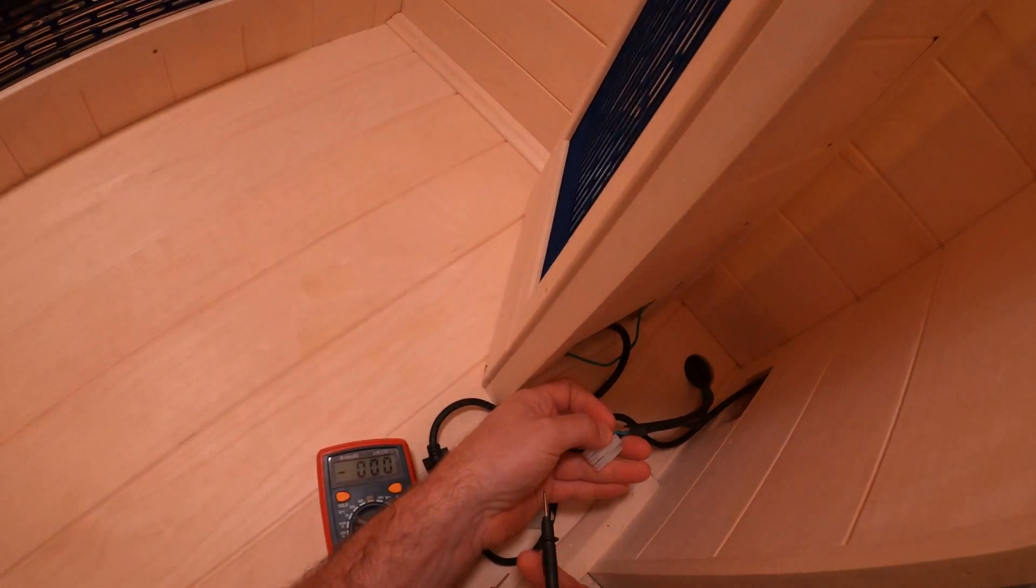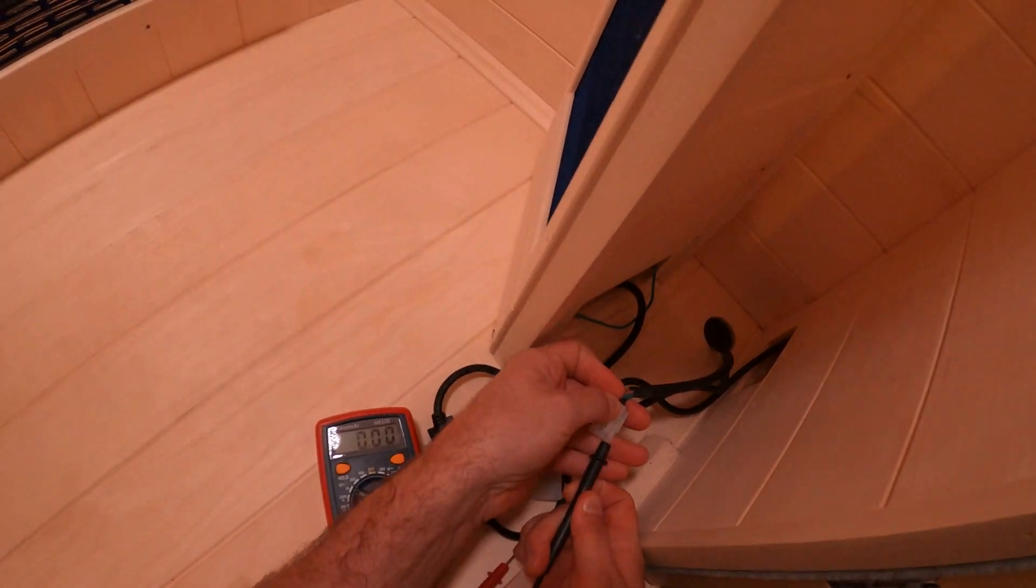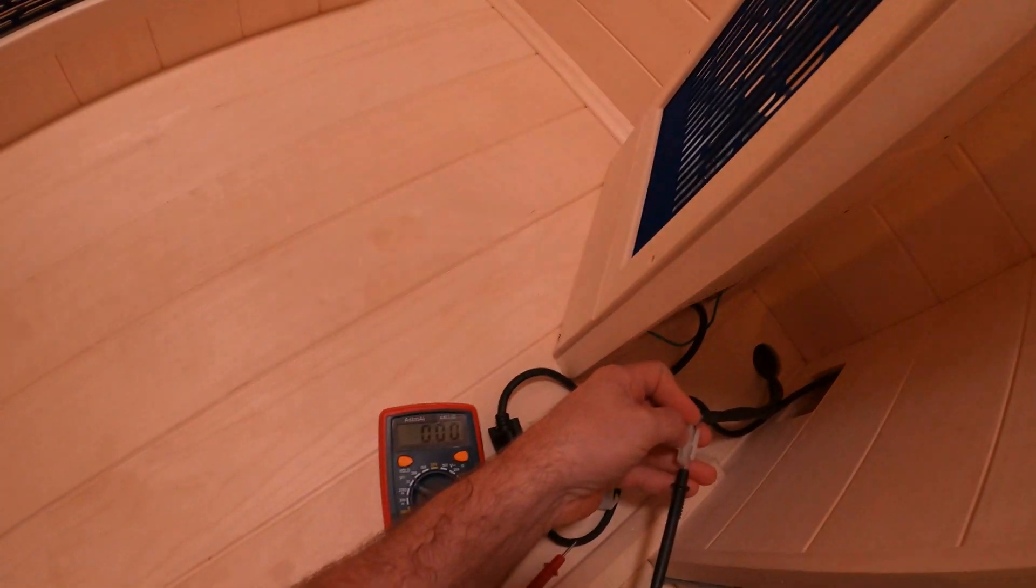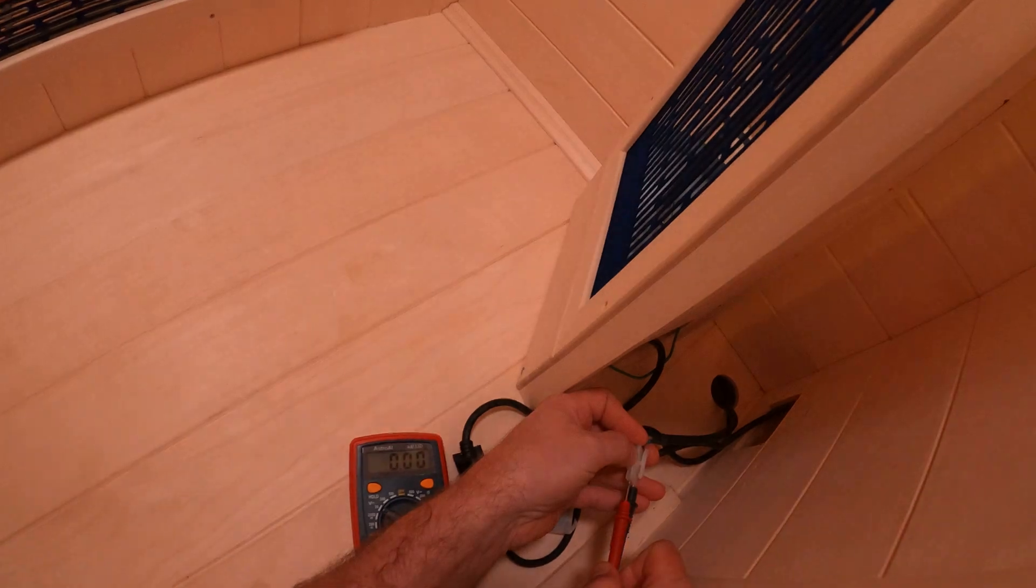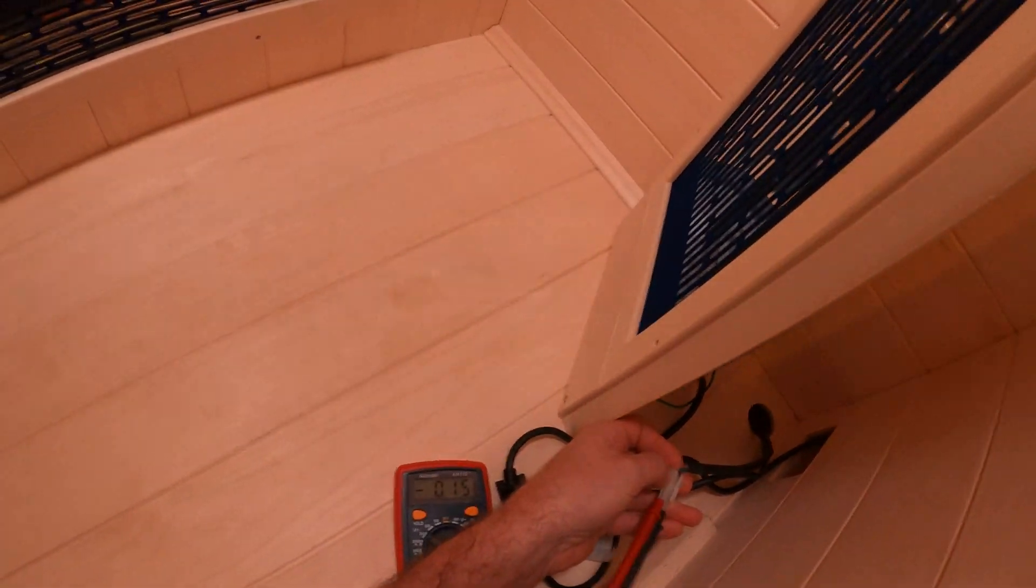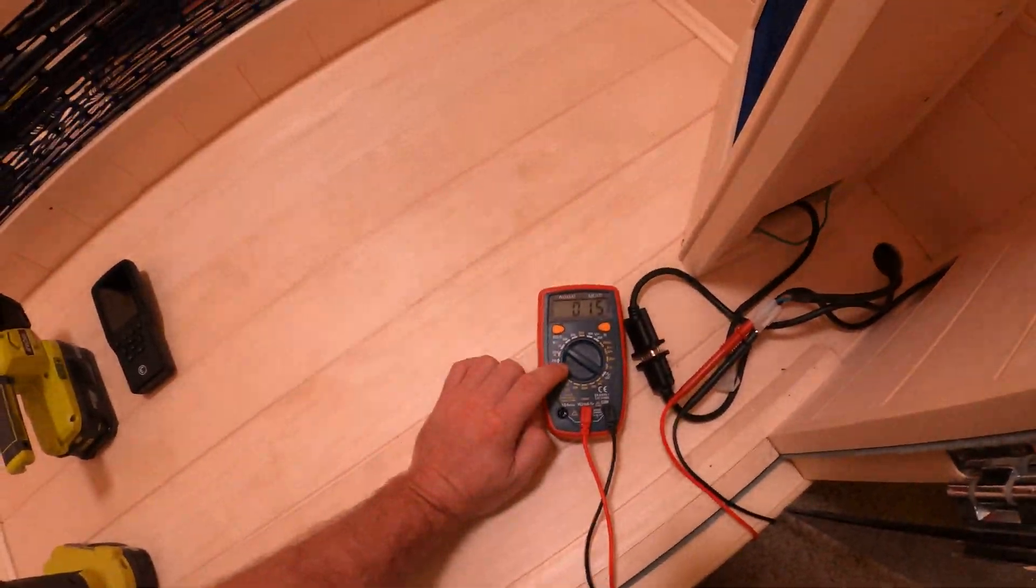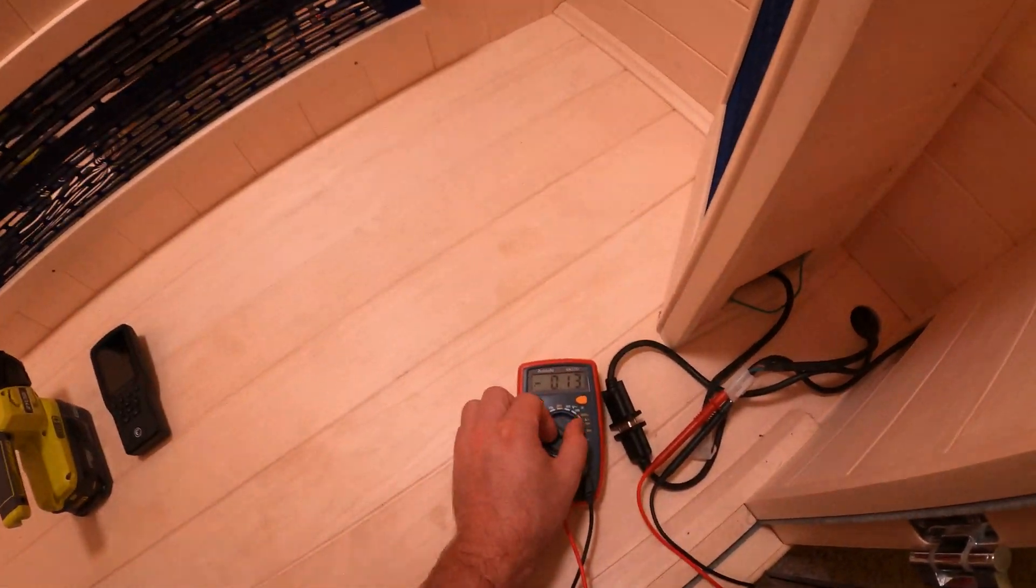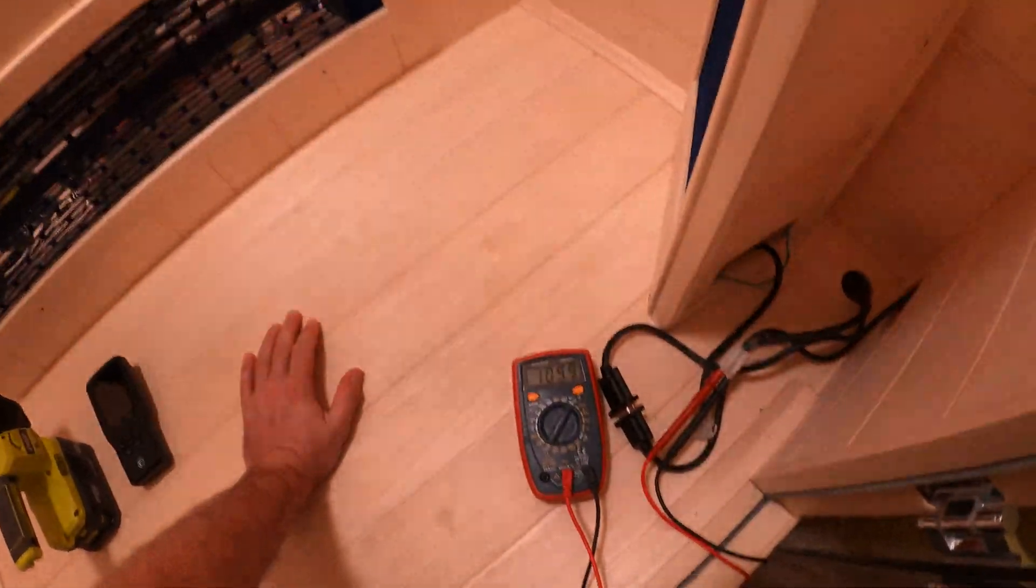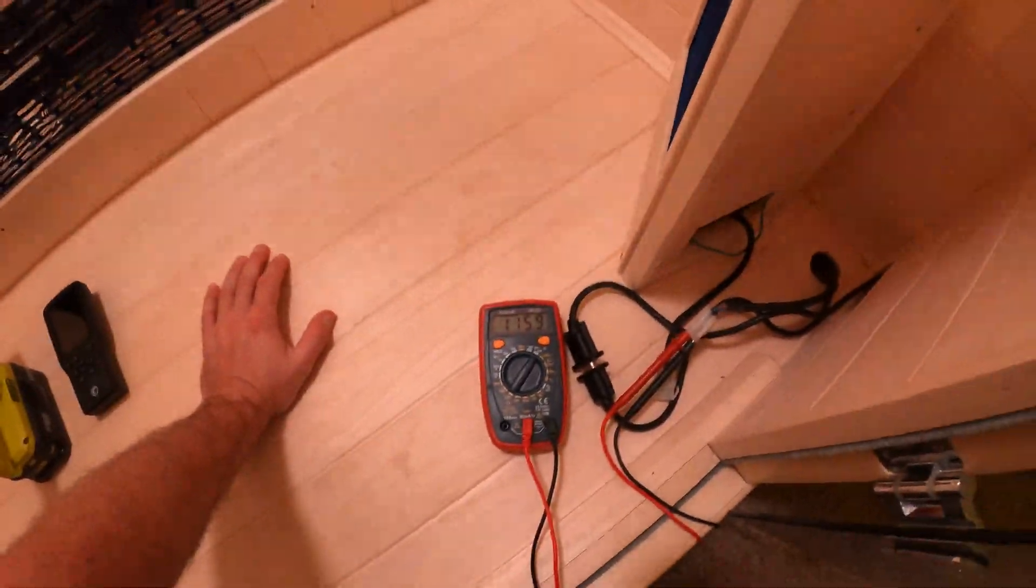If a particular sauna was DC, you would not have AC power at the heaters. So I have this heater unplugged and I was diagnosing it. We've got this little meter on DC right now, showing nothing. If we switch to AC, we can see that we've got 115 volts.